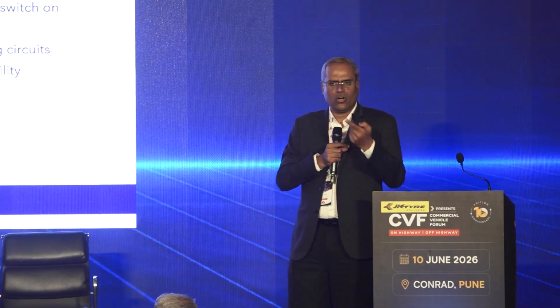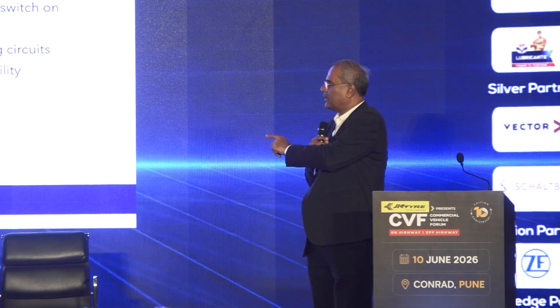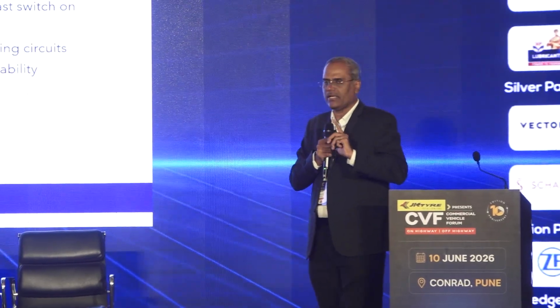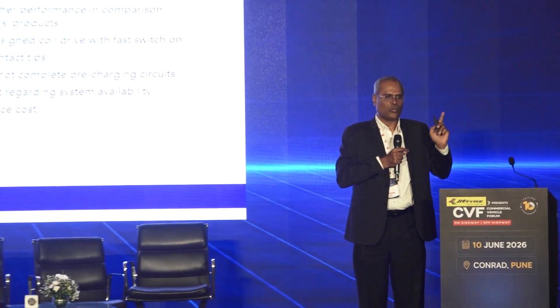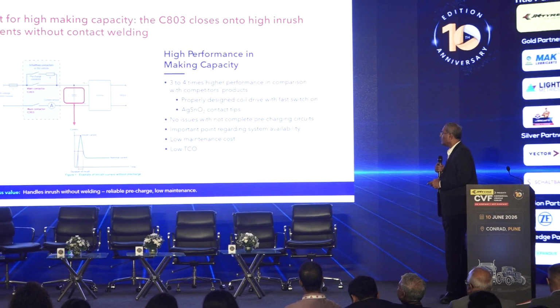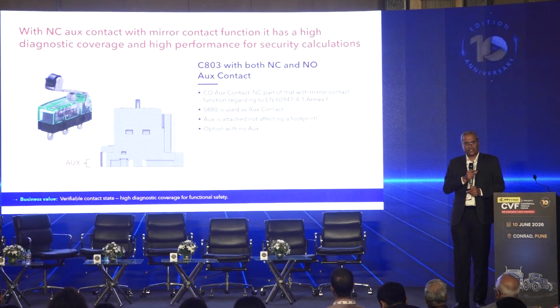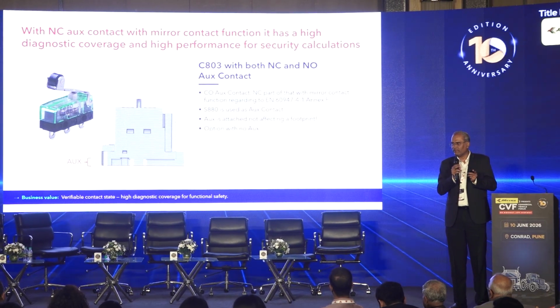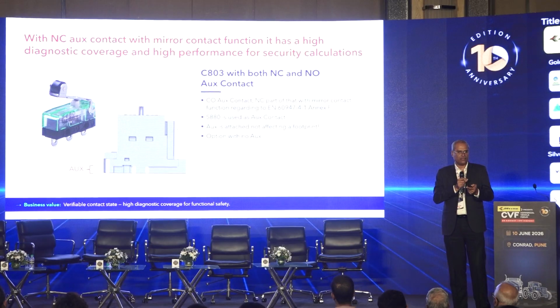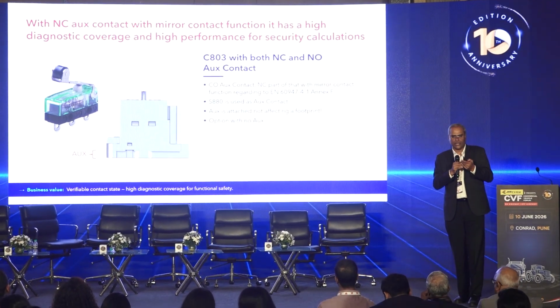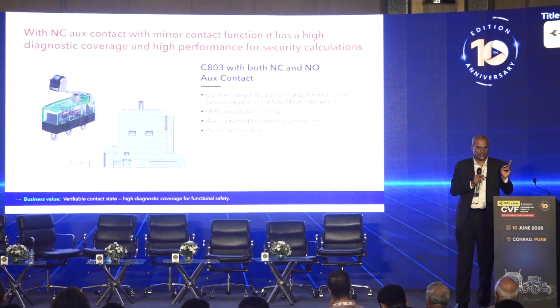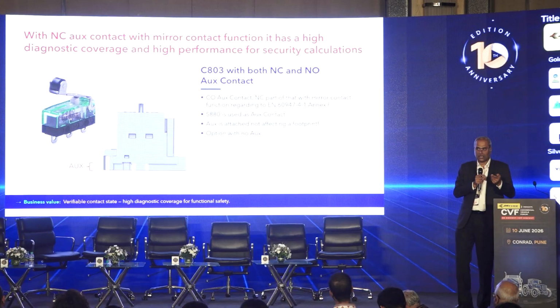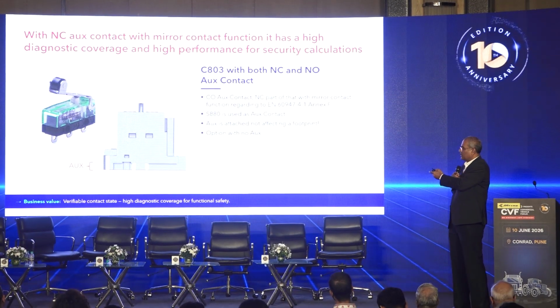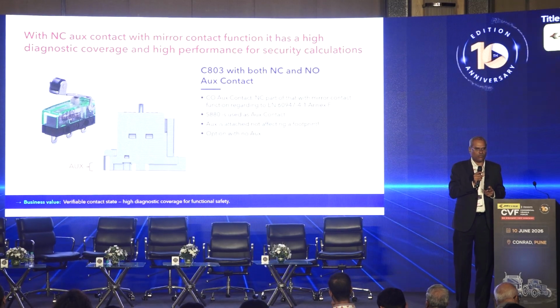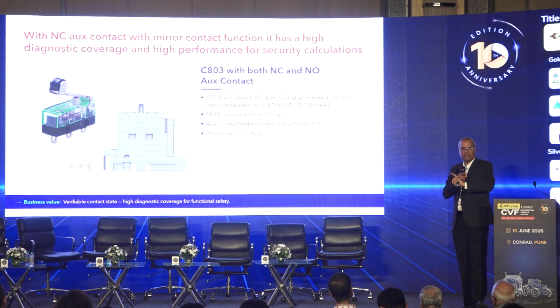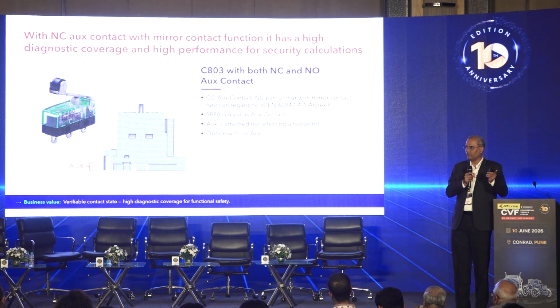On the same level, when you switch on and there is a high inrush current, the air insulated technology is able to handle that, whereas the gas insulated technology will primarily need the inverters to switch off the current first and only then operate. The next important element is that in gas insulated technology, because it is a hermetically sealed device, you cannot check the actual true contact position. If the contactor is welded, you will still get a wrong signal to your BMS that the contactor is on and off depending on the command. But with air insulated technology, the way Schaltbau has it, there is a mechanical indication for the auxiliary switches. So you get the true contact position indication in your BMS at all times.